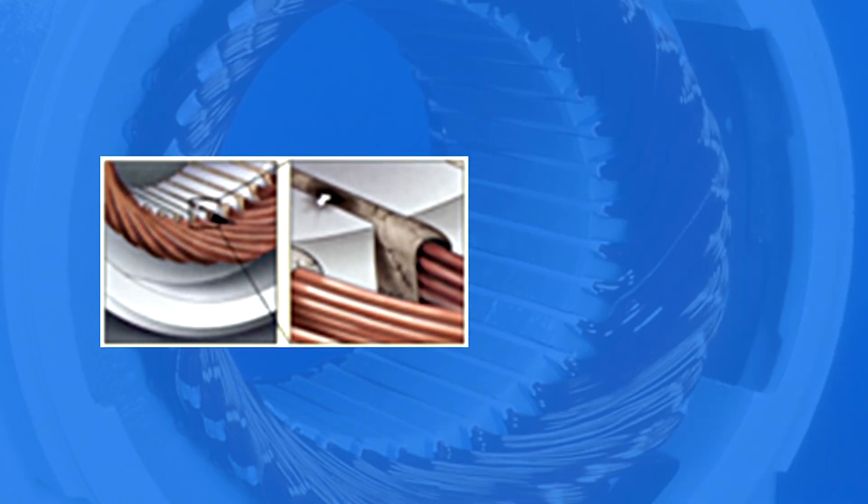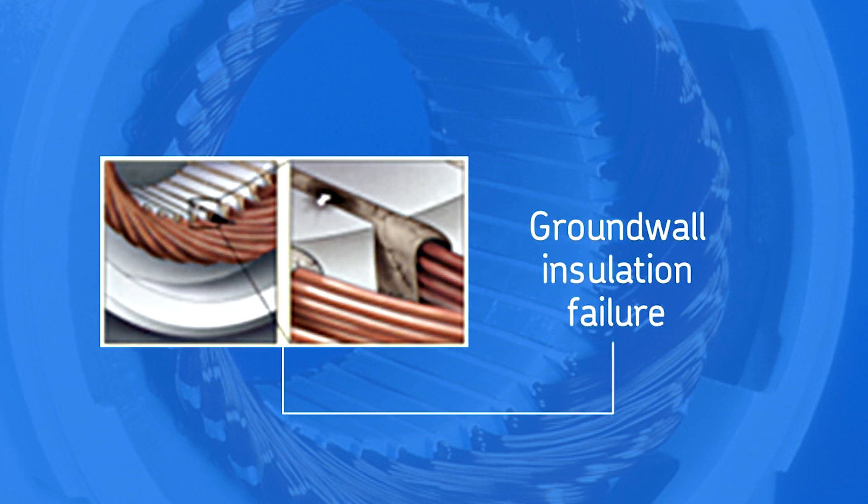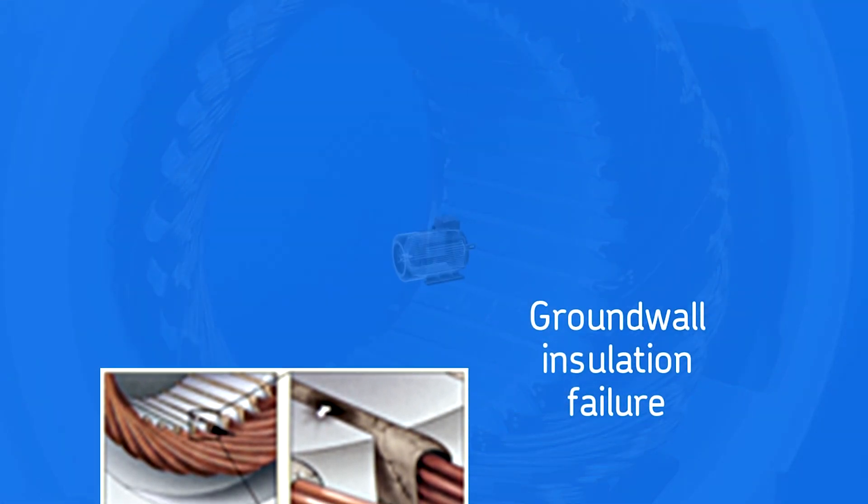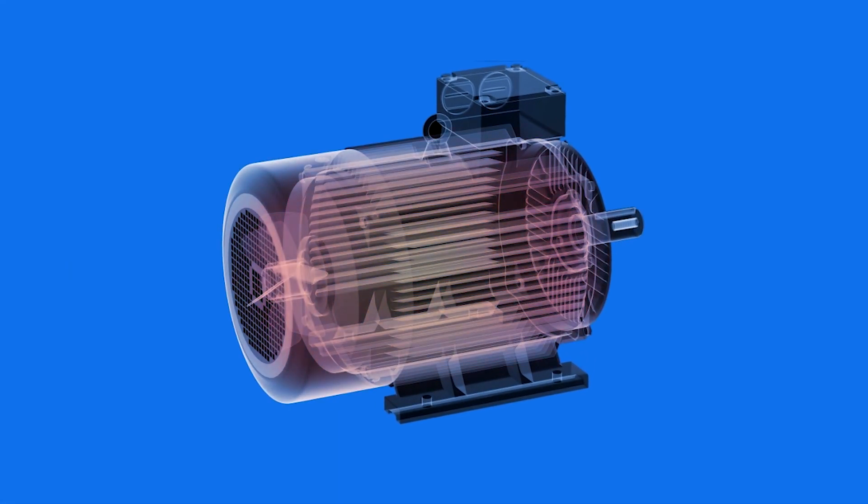When the insulation fails and there is a path to the core, it is called a ground-wall insulation failure since the stator core is at electrical ground. Often, when a motor overheats or has a turn-to-turn failure, the excessive heat will cause a ground-wall insulation failure also.